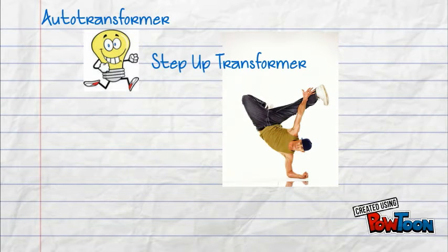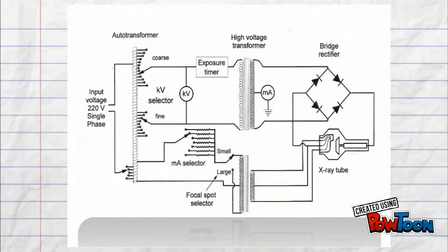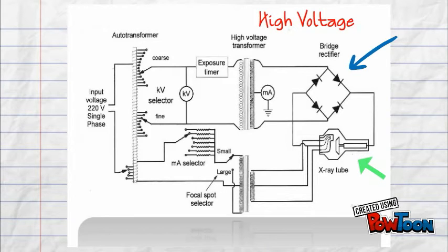Now we're moving on to the secondary high voltage side of the circuit. On the high voltage side, the electricity has a decreased output and an increased voltage. This travels through the four diode rectification circuit and then into the X-ray tube on the anode side.